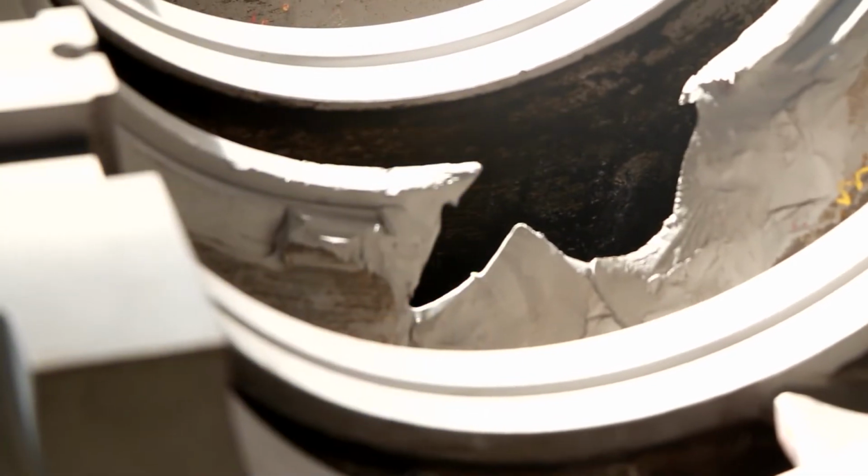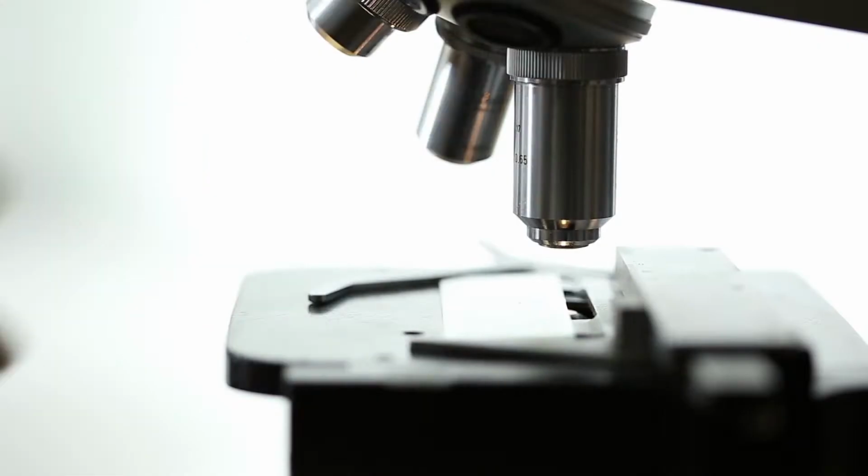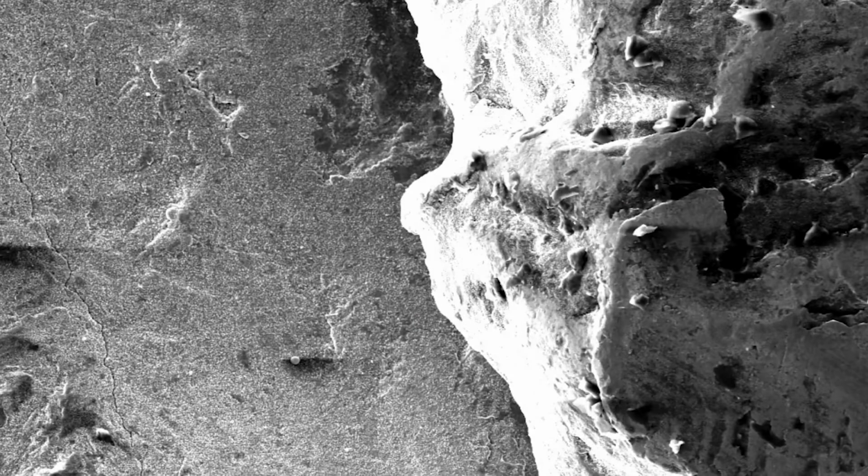The forensic and metallurgical analysis was done to verify that there were no problems in the previous welding on this casing. After doing our root cause analysis and metallurgical examination, we determined there was not a failure due to welding of the volute, but it was a failure due to the casting of the volute.